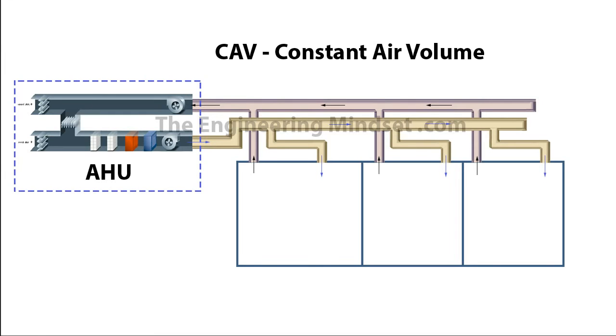From this schematic representation of the CAV system you can see just how it's connected. All the rooms are connected to this main duct, and the only form of temperature control is in the main AHU. That means all these rooms receive the same tempered air at a constant volume. Note that you do not have to return the air back into the supply ducts — it can be expelled straight out to atmosphere as well.